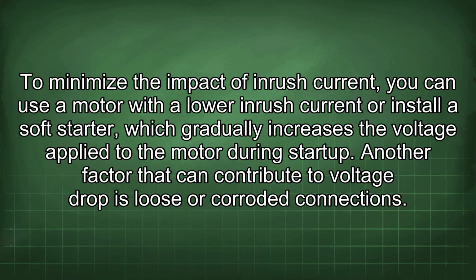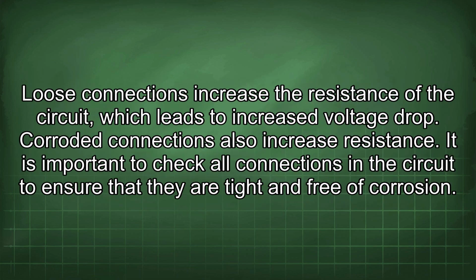Another factor that can contribute to voltage drop is loose or corroded connections. Loose connections increase the resistance of the circuit, which leads to increased voltage drop. Corroded connections also increase resistance. It is important to check all connections in the circuit to ensure that they are tight and free of corrosion.